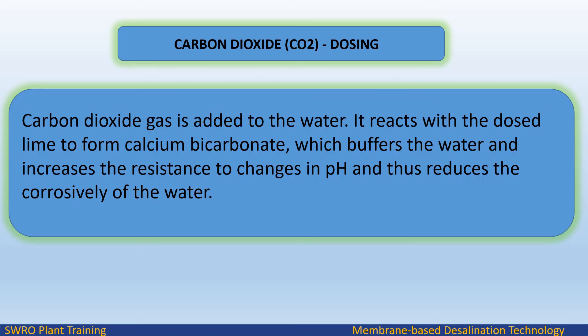Carbon dioxide (CO2) gas is added to the water. It reacts with the dosed lime to form calcium bicarbonate, which buffers the water and increases the resistance to changes in pH, and thus reduces the corrosivity of the water.